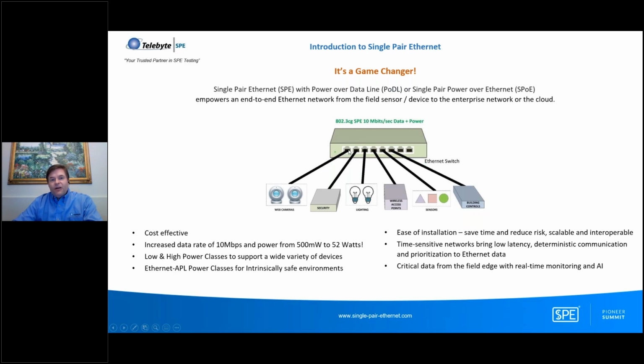However, if you look closely here, these equipment on the end of the ports, instead of an 8-wire Ethernet cable, it's only a 1-pair Ethernet wire with 2 wires. And so that will provide 10 megabits per second, and it will remotely power the end device. So there's no need to have an electrician out to wire up an auxiliary electrical outlet to power these devices.